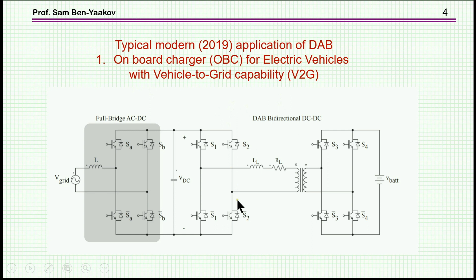On the reverse direction, we have another bridge pumping power into the transformer on this side, which is rectified here to get DC again. Then what was used before as a rectifier is now used as an inverter, producing a sinusoidal current waveform fed to the line. So this is a very typical application of a dual active bridge, which is of great interest today.